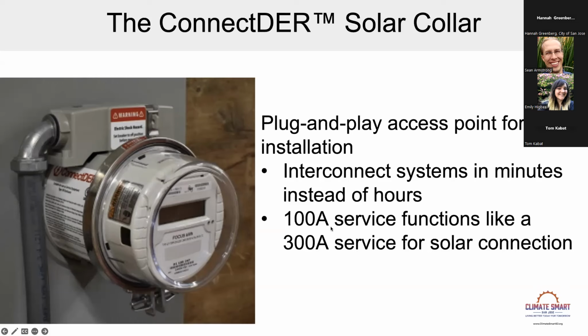And what it does is it takes your 100 amp service and makes it function like a 300 amp service for the purposes of solar connection. Meaning instead of putting 16 amps into your panel, now you can put up to 50 amps in through the meter connection. So if it was 16 amps on a 100 amp service and you can do 50 amps with the ConnectDER, that's about 300, technically like 312, call it 300. So it's about three times as much.